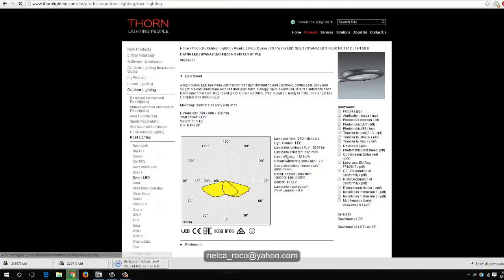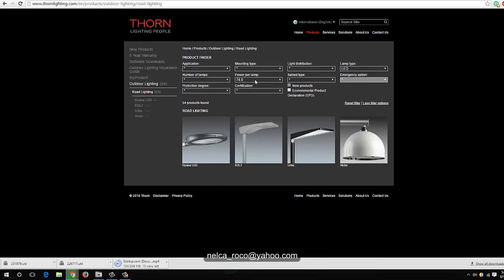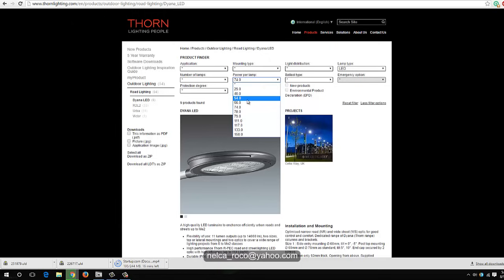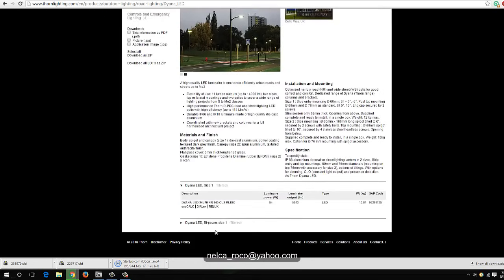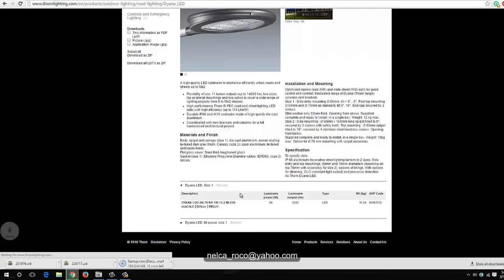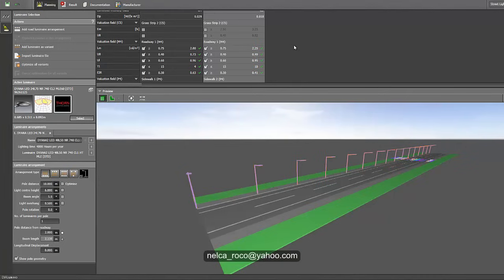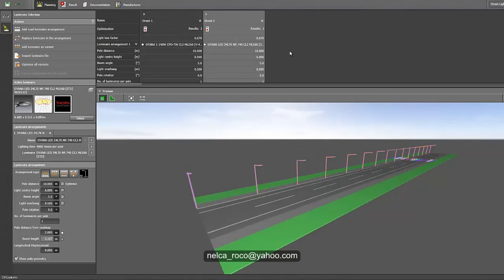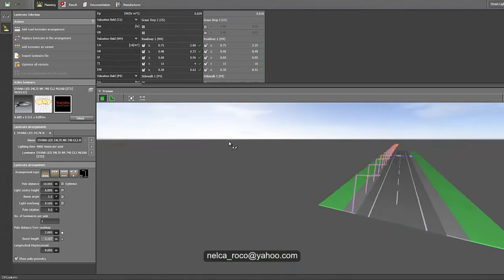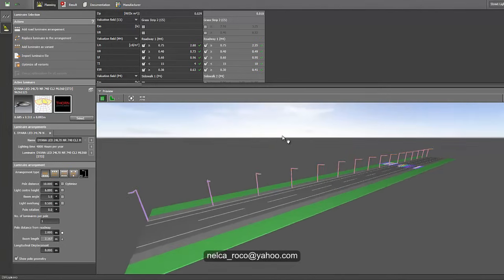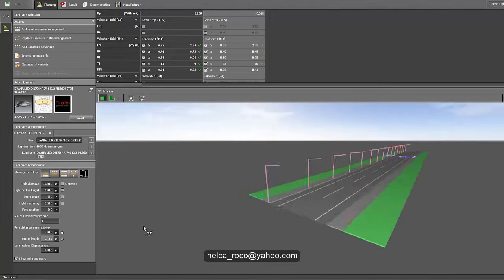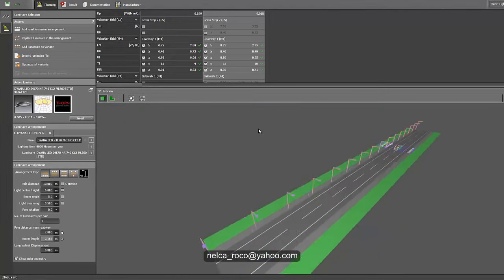What if we also reduce the wattage? Let's select another luminaire — same Dyana LED but at 54 watts, still with the narrow beam. Click and confirm use. Let's replace the existing fitting with the lower-wattage Dyana LED and apply. Run the calculation — and it's still okay. So my subscriber can use even a 54-watt LED luminaire for this configuration.